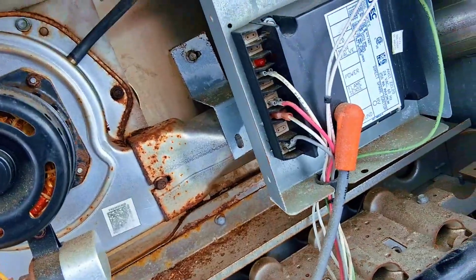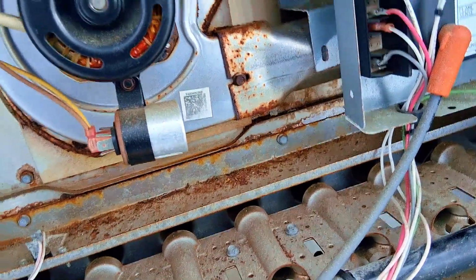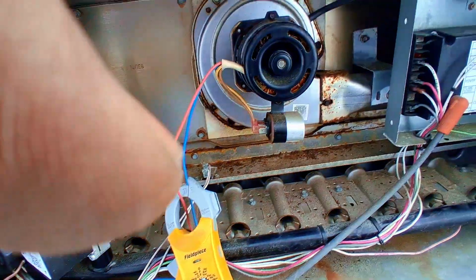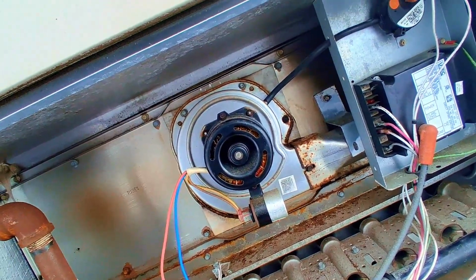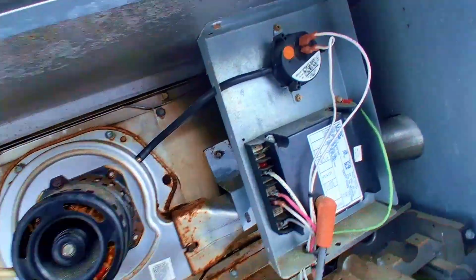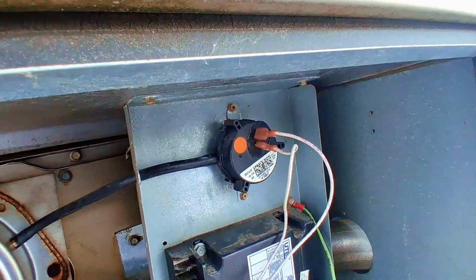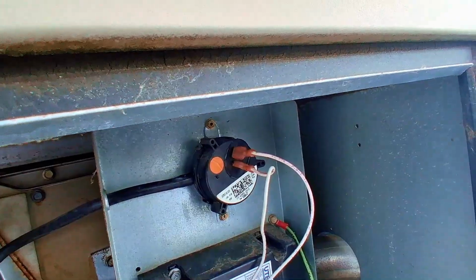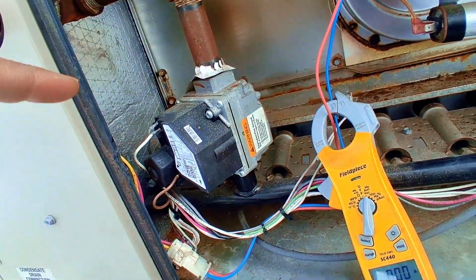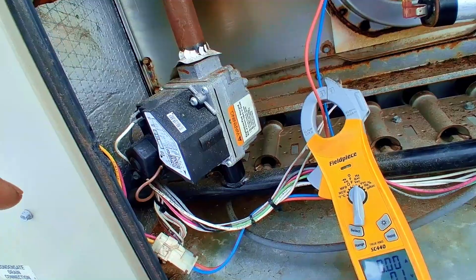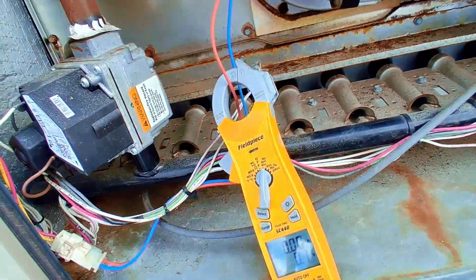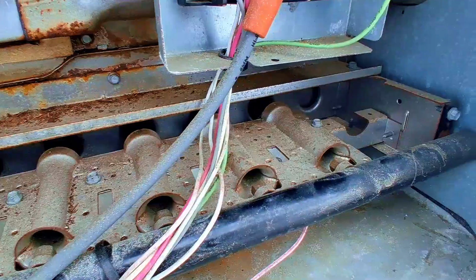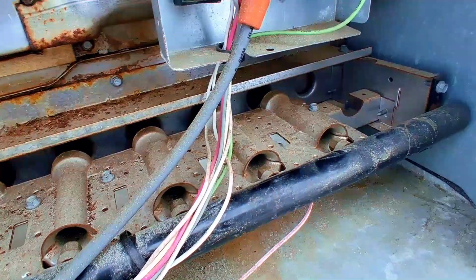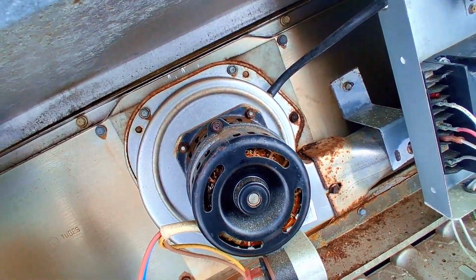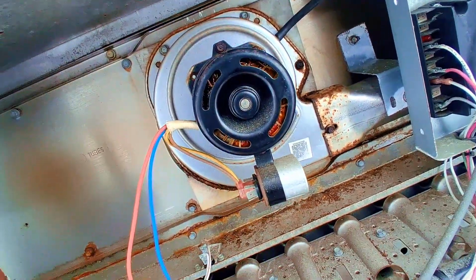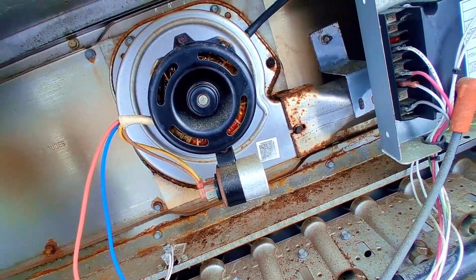That's the only thing about systems like this, different things popping up can make you feel like it's this, then it gives you that the gas valve is not working, which is far from it, because it says the gas valve is not proving. Then you check the flame sensor, it comes back, and then it clicks again saying S18. But that's why, man, you just gotta check everything.